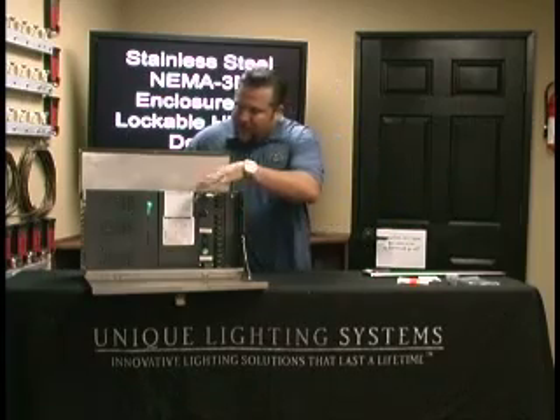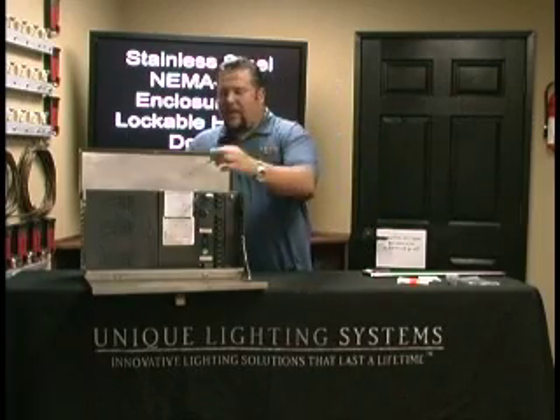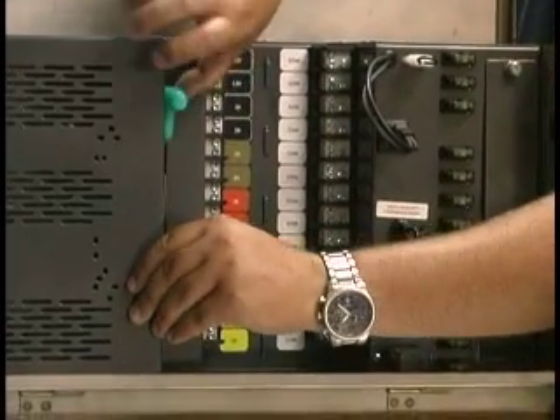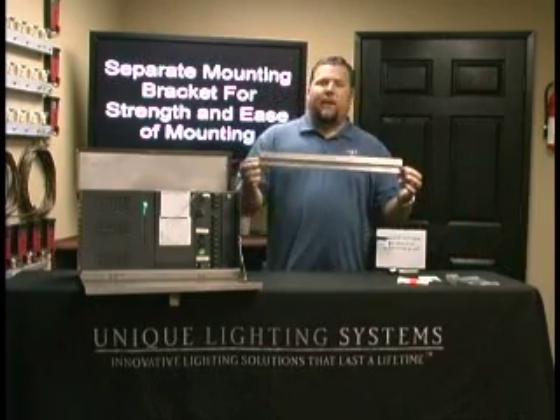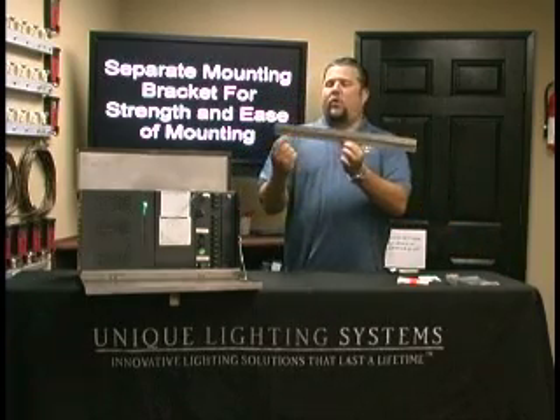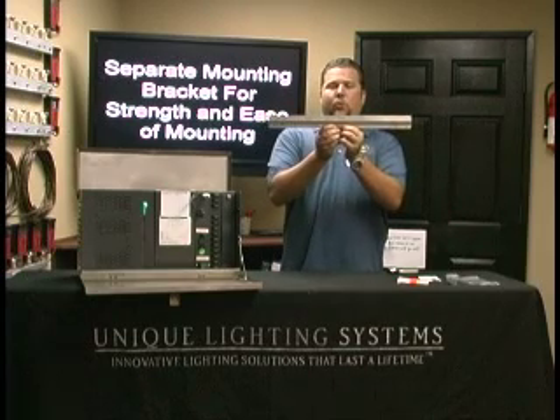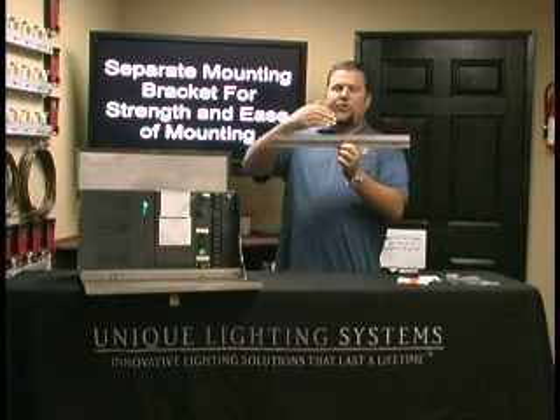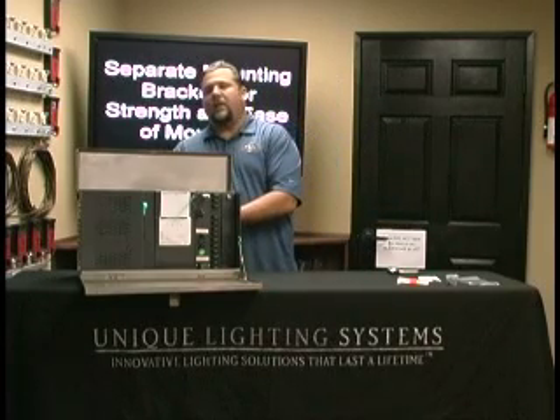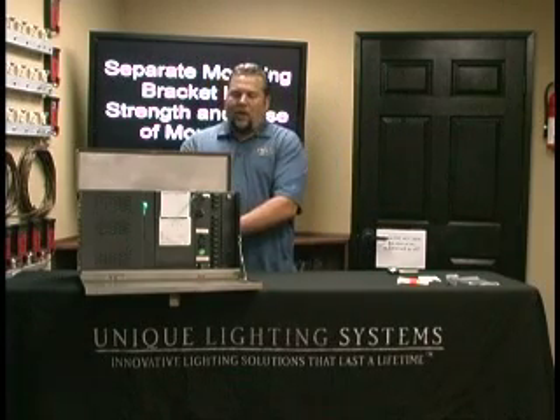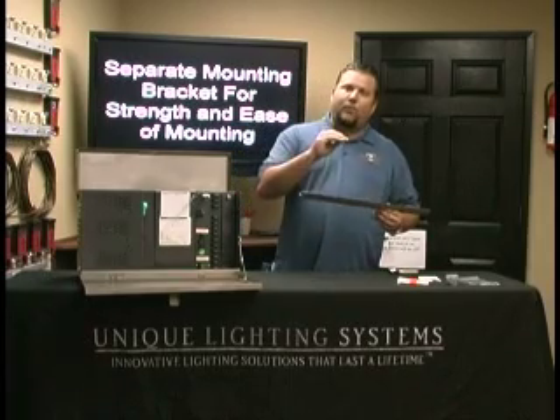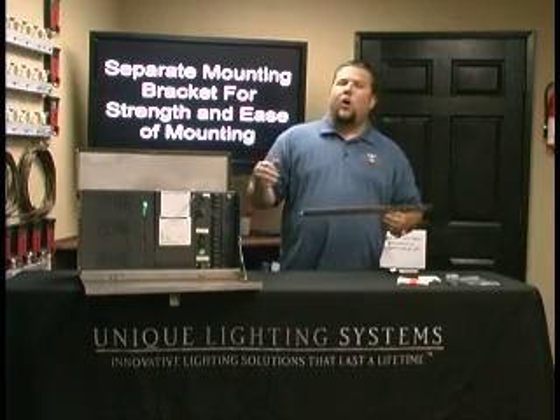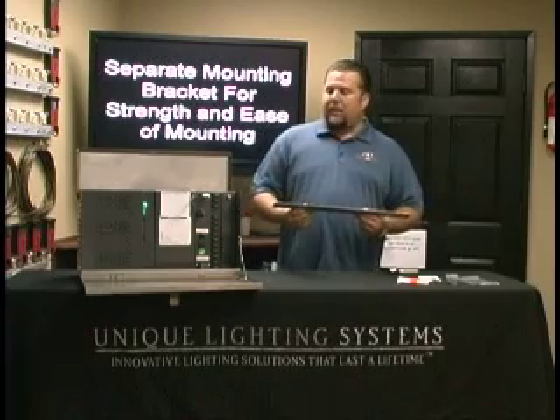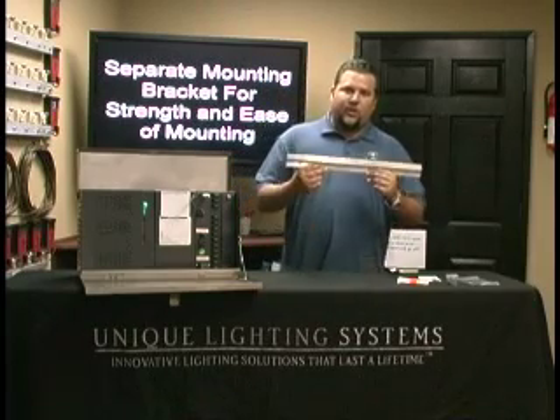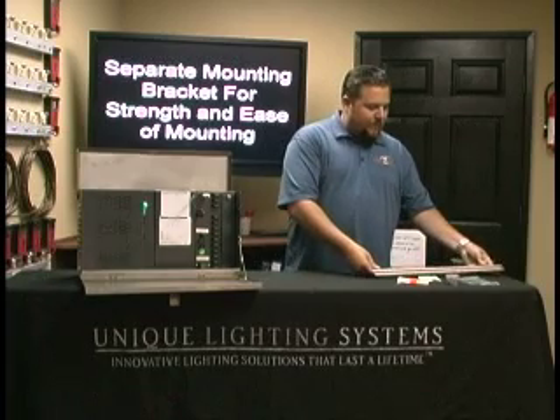As you can see in the layout here, there's lots of really neat features. Right on the inside is a hex key tool for your Allen head. The unit will be provided with this stainless steel mounting bracket. So how this works is you'll see there's 4 holes here for you to put your anchors and drill into the wall. This will mount, and then the transformer has a really nice slot on the back side here that will just lock right in place. On the bottom of the transformer is also another third anchor point for you to put this transformer on the wall without fear of it being able to move, wiggle, and come loose. It is a large, heavy unit, so this bracket's a must, and it makes mounting really easy.